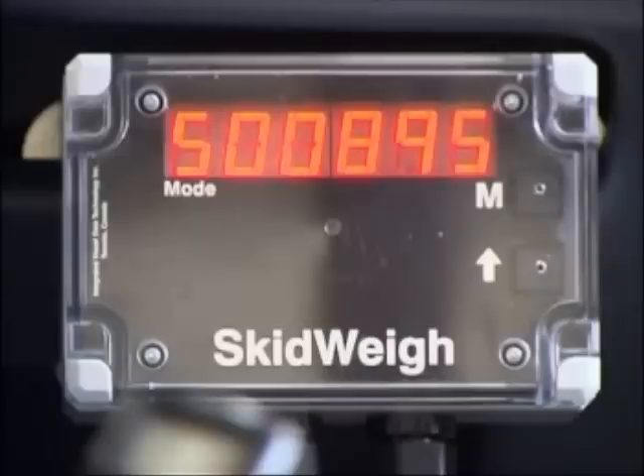If the forklift had previously been calibrated with a 4 or 5 digit number, you must use the paper clip and the method above to return these digits to 0. As you can see, we have entered a valid calibration of 895, in this case kilograms. The display shows the number 5 in the mode window, and the rest of the display shows 00895. Before you go to mode 6, make sure that your known weight is loaded on the forks and the forks are lowered to the ground. In our case, 895 kilograms.